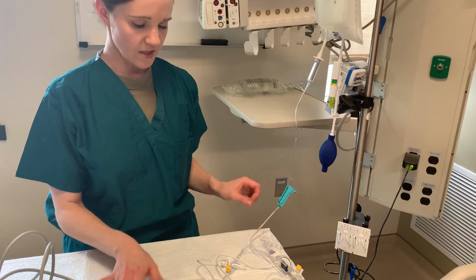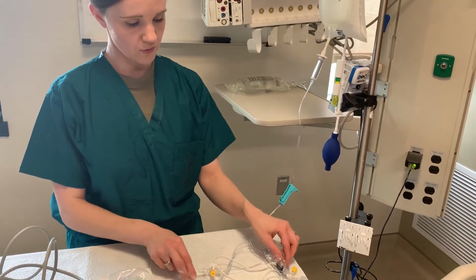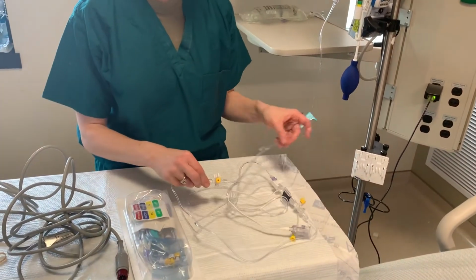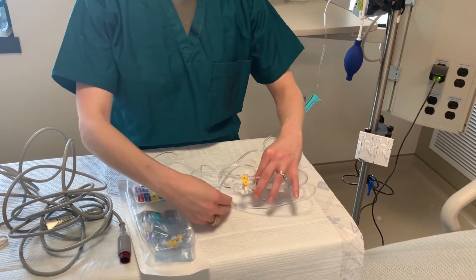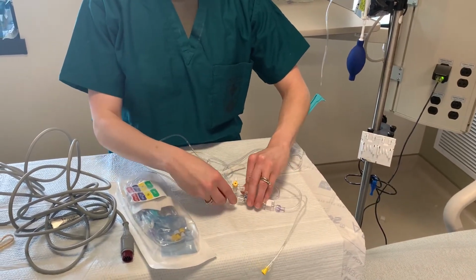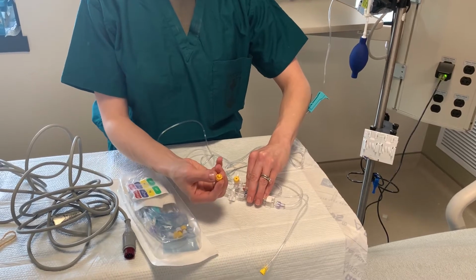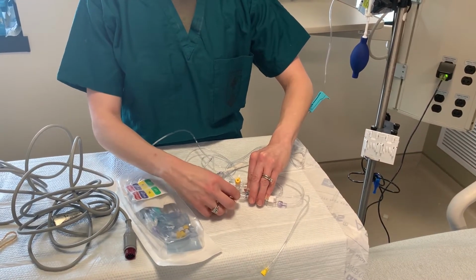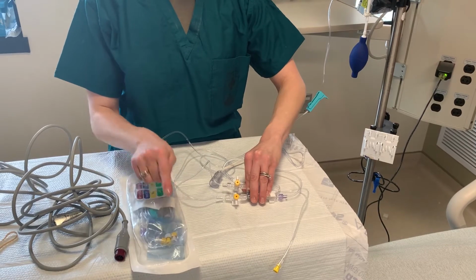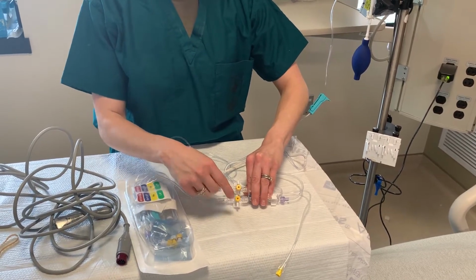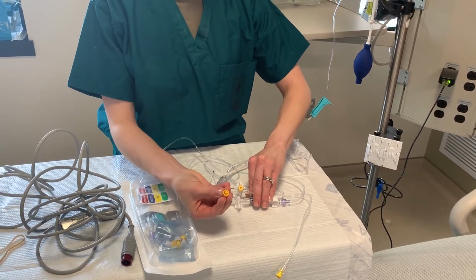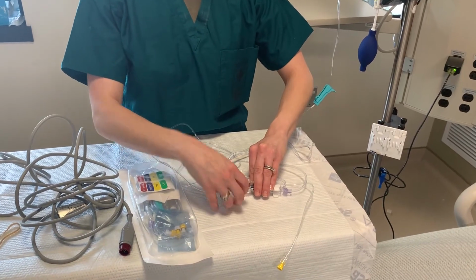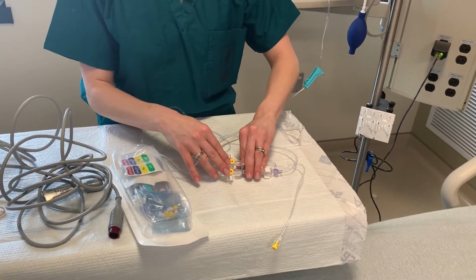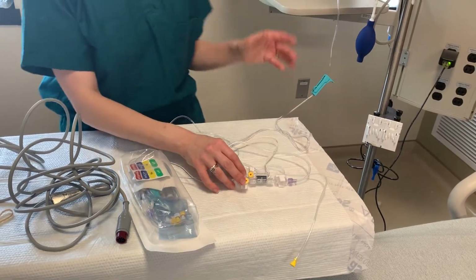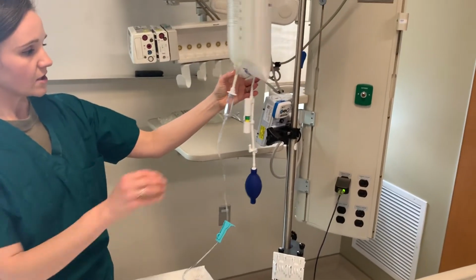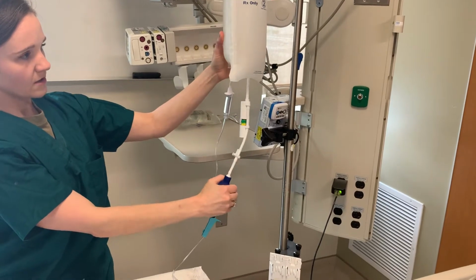After you get it out of the package, you also want to make sure that these ports here, there are two ports that will come with white caps on them. Those white caps do have holes, so the fluid will come through those holes. So after you open your package, you want to change the white caps to the yellow caps. The yellow caps are solid, and when you put those on and you prime your line, fluid will not flow out of those caps.